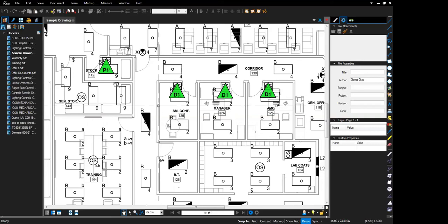And again, the reason for mixing them up like this is a cost thing. In a room like this general storage, where it's L-shaped, if you put passive infrared here, someone's going to come in and it's going to trigger the sensor. But then if they get back here and start doing something, working, stacking a shelf, whatever it may be, the light's going to turn off on them, because it won't be able to see them around this corner.